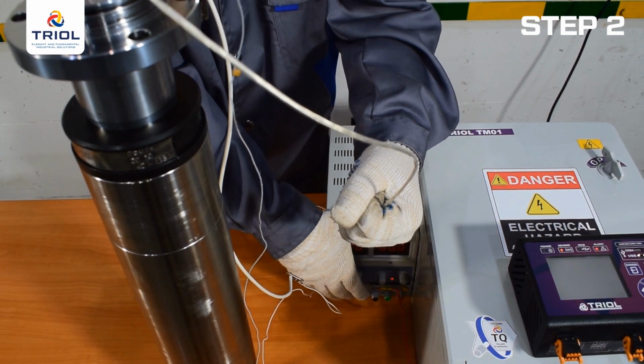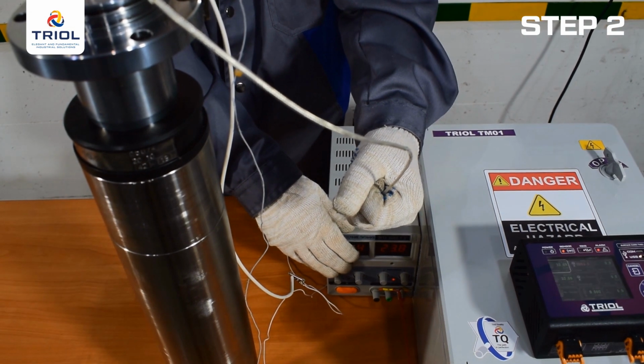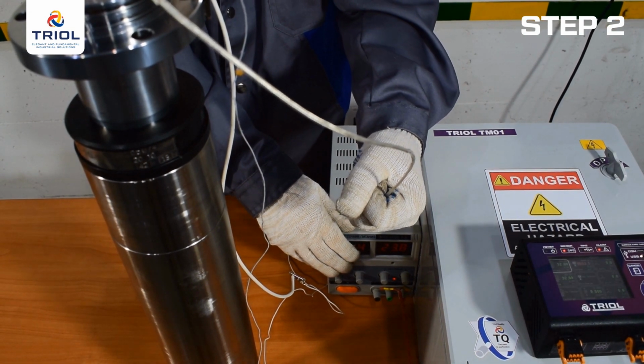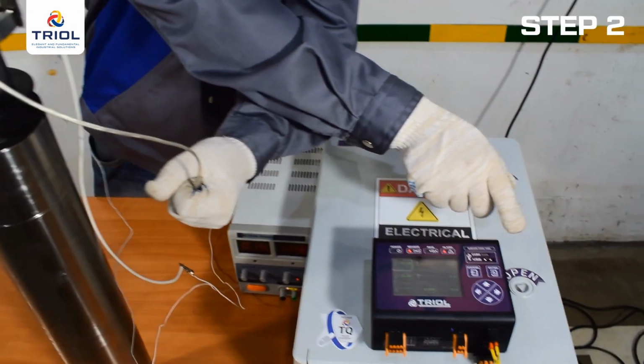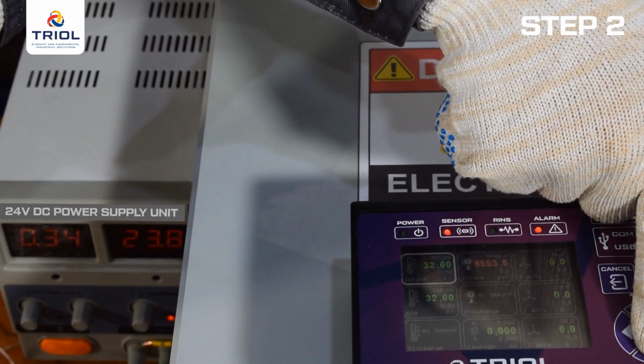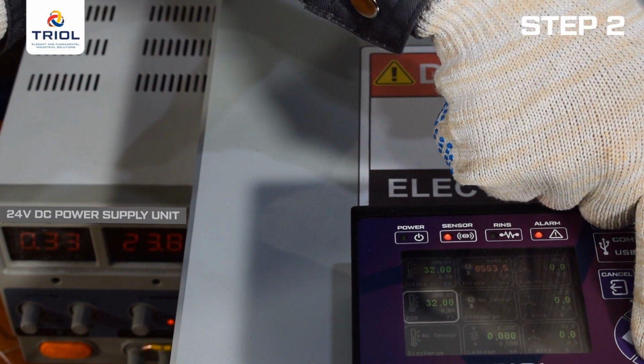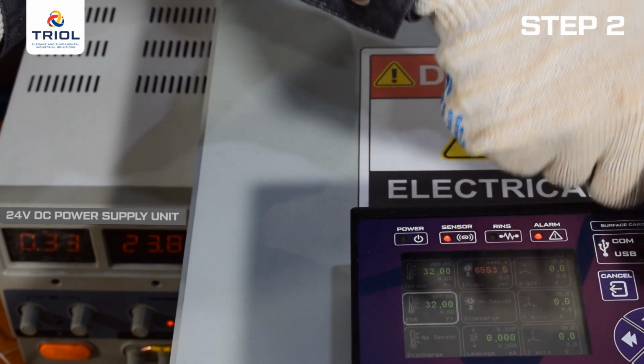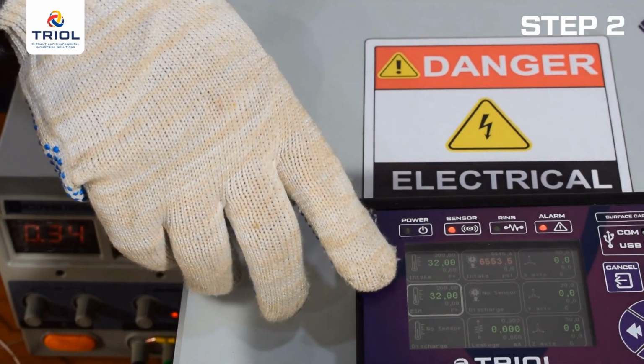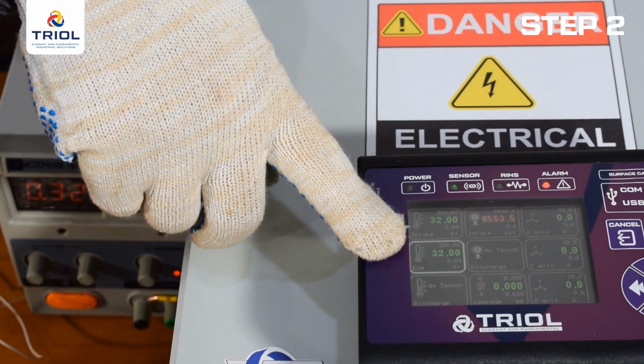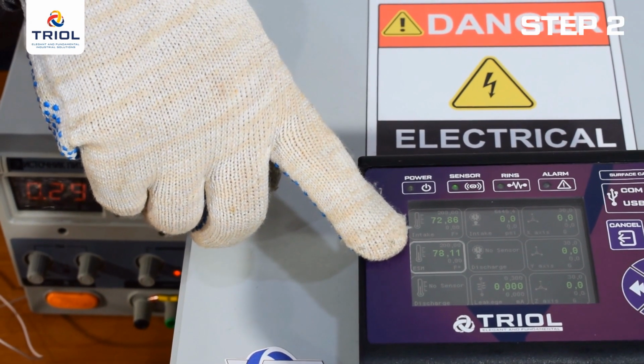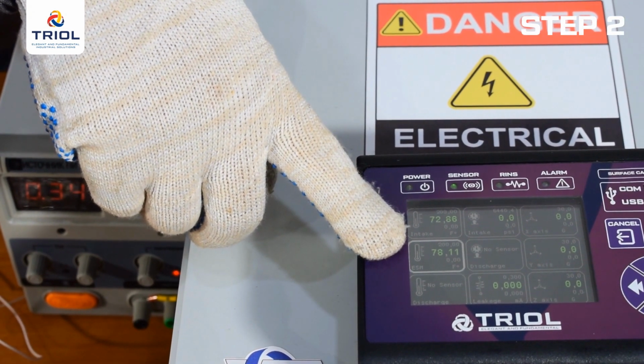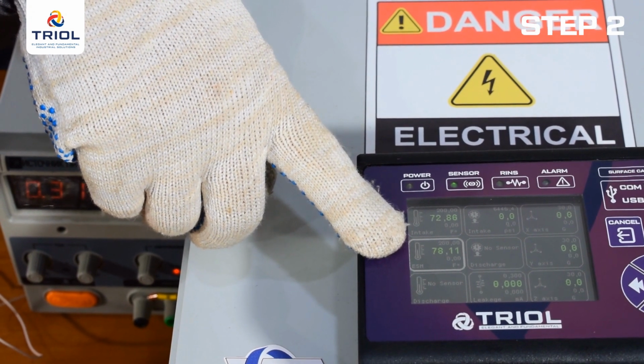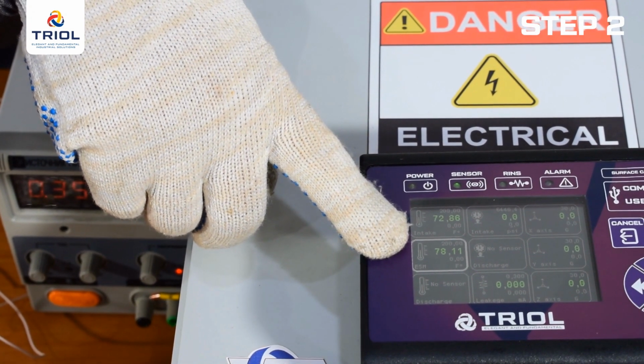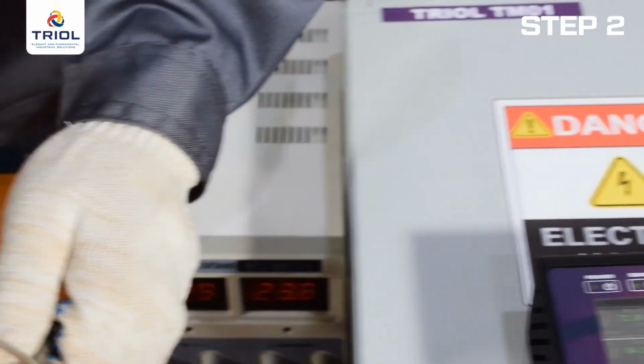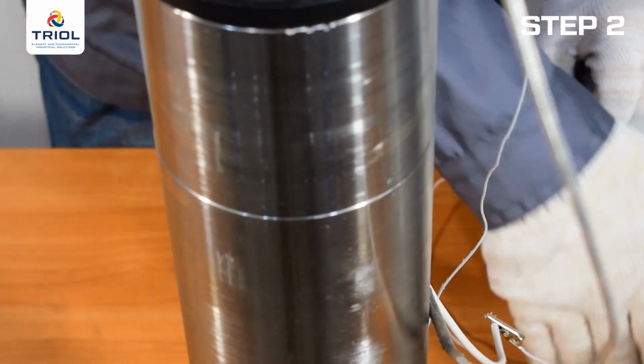The warmth of your hand will begin to warm it up, and thus you can determine that the submersible unit is transmitting measured data to the surface card. The same will happen with vibration if you slightly shake the TM01-10-S. Please check that the card screen is lit up and the temperature, pressure, and vibration values turned green, which means that the connections and the sensor itself are working properly. After making sure everything is in order, turn off the power supply and disconnect the clamps from the cabinet and the 0 wire.